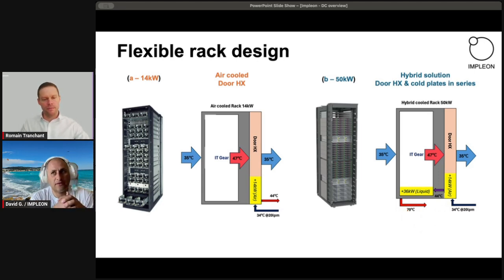That means to achieve 70 degrees, we need a heat pump, which will allow us to elevate this temperature, useful for district heating. However, in liquid cooling, we can achieve that without additional energy consumption for the pump with heat pumps, and that allows us to provide valuable temperatures at the same level requested by the district heating operator, and that thermal energy can be paid for. So when you have low grade heat, it's not so easy to get money for that. But when you have high grade heat, the probability that you will be paid for that is much higher.